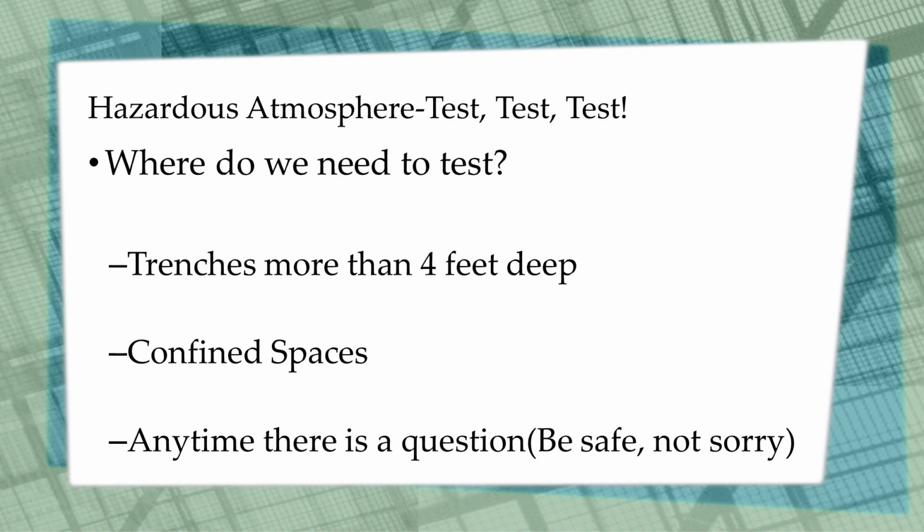In particular, trenches more than 4 feet deep, we want to test those. We want to make sure there's enough oxygen there, no explosive atmospheres, no hydrogen sulfide, no carbon monoxide or carbon dioxide either. Carbon dioxide does not tend to be as deadly as carbon monoxide, but it still can make you sick. So we want to test for that too, especially trenches near the roadways, where automobiles are continually pumping stuff out the tailpipes, so we make sure none of that congregates down in the trench where we're working.